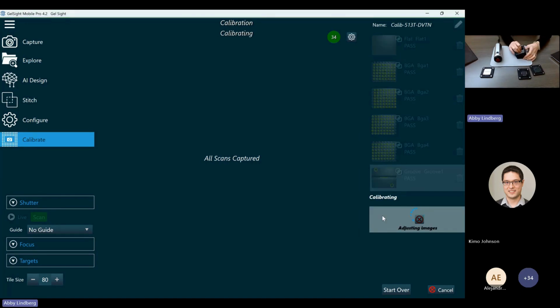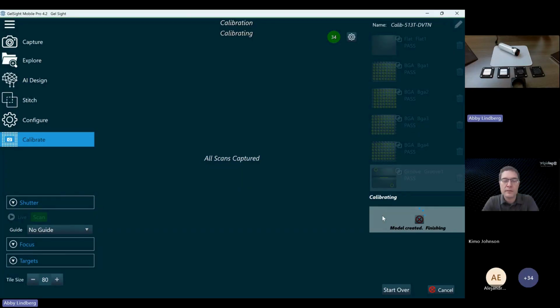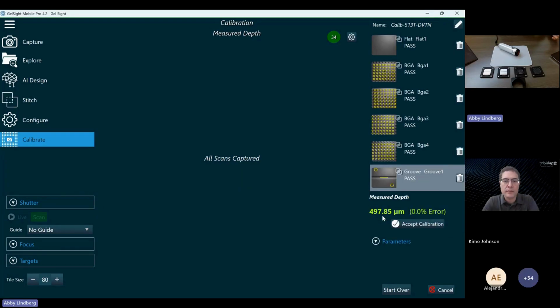Each gel needs to be calibrated before you can use it. You don't have to calibrate the gel each time you connect it to the system, just that one initial time before it's used. However, we have some customers that have a requirement that they need to verify that the system is performing accurately every time they use it, or maybe even every certain number of scans or monthly even. And that's where the validation plate comes into place. So we'll get into that next.